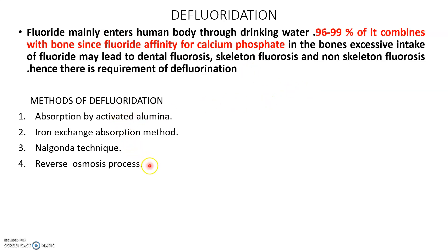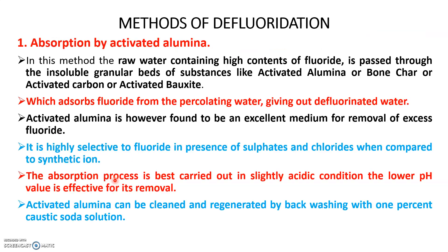There are various methods for defluoridation. The first is absorption by activated alumina, then ion exchange process, Nalgonda technique, and reverse osmosis. For absorption by activated alumina, water is passed through a granular bed of activated alumina, bone char, activated carbon, or activated bauxite. When you percolate the water through those beds, the water comes out defluoridated — defluoridation takes place.